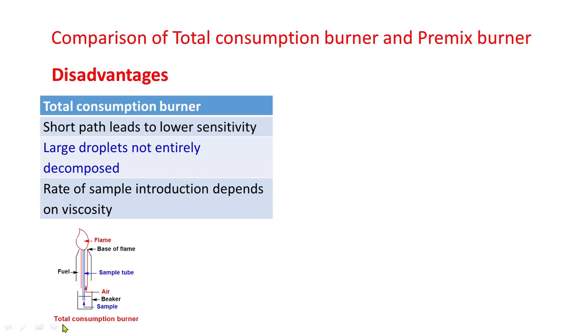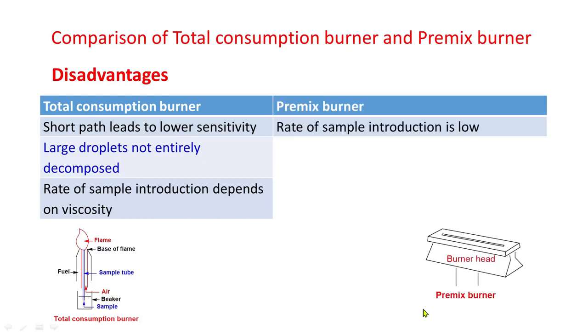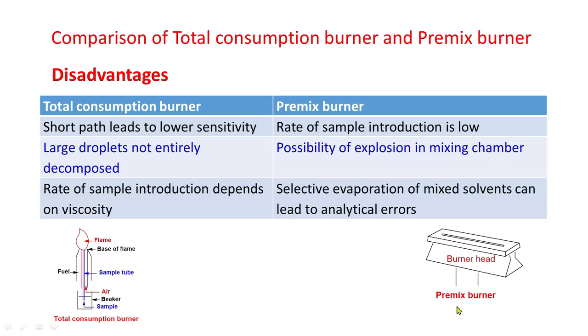Regarding disadvantages: the total consumption burner has a short path length and hence lower sensitivity. Large droplets are not entirely decomposed in the flame, and the rate of sample introduction depends on the viscosity of the solvent. For the premix burner, the rate of sample introduction is low, there is a possibility of explosion in the mixing chamber, and selective evaporation of mixed solvents can lead to analytical errors.